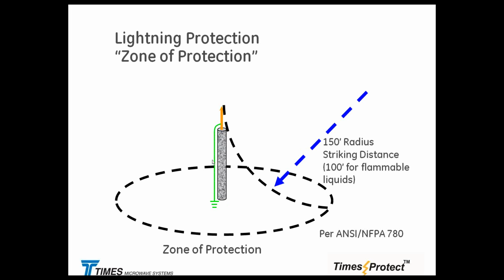But I would rather take the money, basically, and put that copper underground in the form of radials to move the step potential rise away from the tower if I have the real estate, and basically roll it this way as opposed to rolling into the shelter and into the equipment. So here, remember when you're talking about the rolling ball theory, that's the electromagnetic field, kind of coming down in the form of that step leader. And then once you are going to have the current flow, you are going to have basically the outskirts of that whole imaginary ball, whatever it touches is going to be subject to a current attachment point and a discharge.